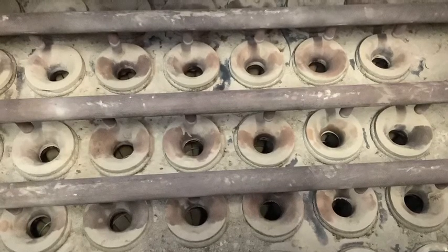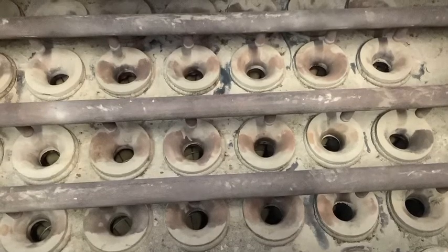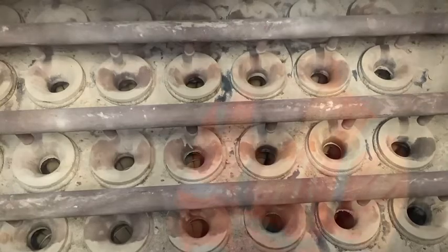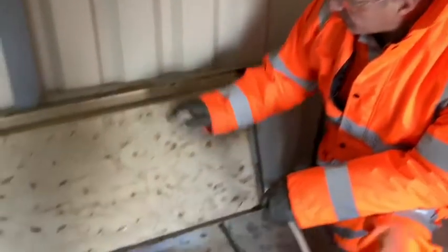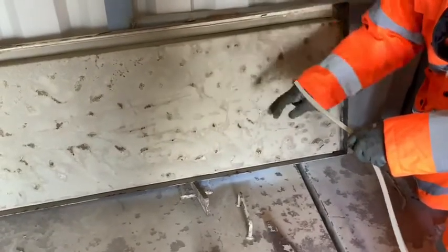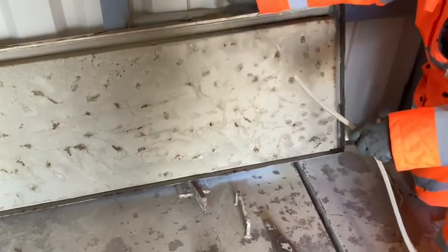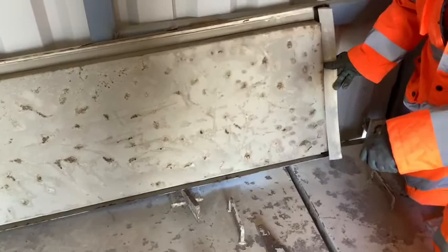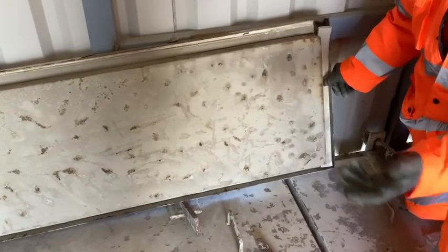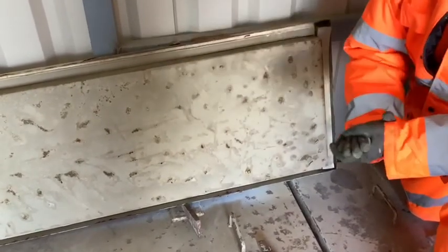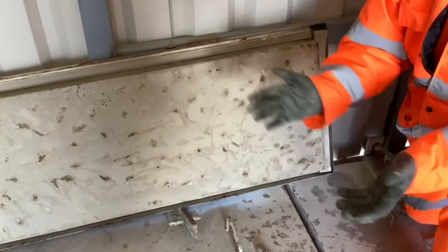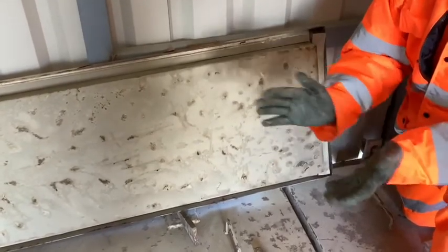You can also see in this example some historical filler, so the best practice will be to remove it. While we're inspecting this lid, now it's off, you see evidence of historic dust. Seals are in place around, but we just found this one. It's missing on this corner, so we just need to attach it. Again, good practice would be to sandblast all this off, grind it off, and then paint it black to be able to see any fugitive release of filler during production.